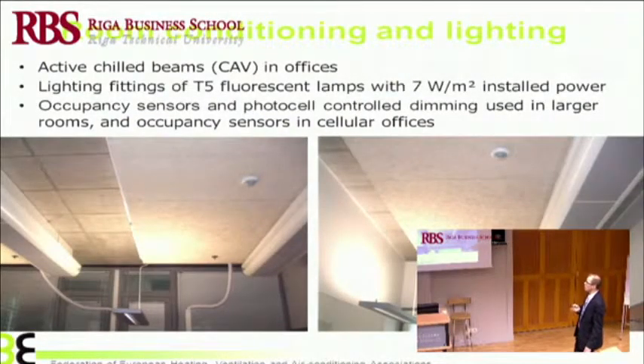On the room side, you see for the room conditioning, these are active chill beams, so they both serve supply air and cooling when needed, and there is a conventional lighting system. It's not the LED lighting, but this is with these conventional T5 lamps. Still the installed power is quite low. And actually the lighting is also one new question for HVAC engineers. You need to be able to understand and to cooperate with the electric designer in order to find relevant solutions for such high performance buildings.